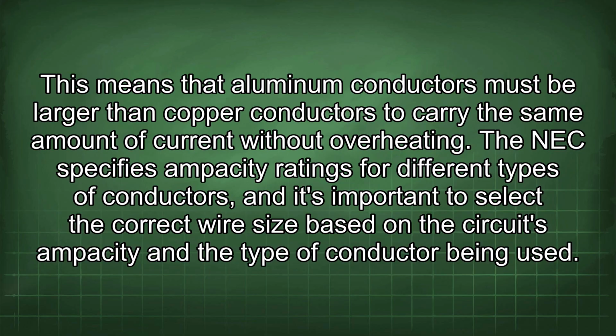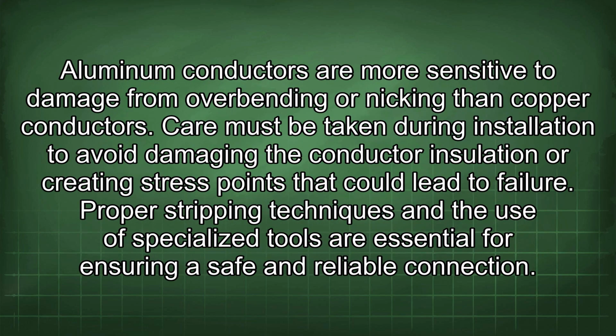This means that aluminum conductors must be larger than copper conductors to carry the same amount of current without overheating. The NEC specifies ampacity ratings for different types of conductors, and it's important to select the correct wire size based on the circuit's ampacity and the type of conductor being used. Aluminum conductors are more sensitive to damage from overbending or nicking than copper conductors. Care must be taken during installation to avoid damaging the conductor insulation or creating stress points that could lead to failure. Proper stripping techniques and the use of specialized tools are essential for ensuring a safe and reliable connection.